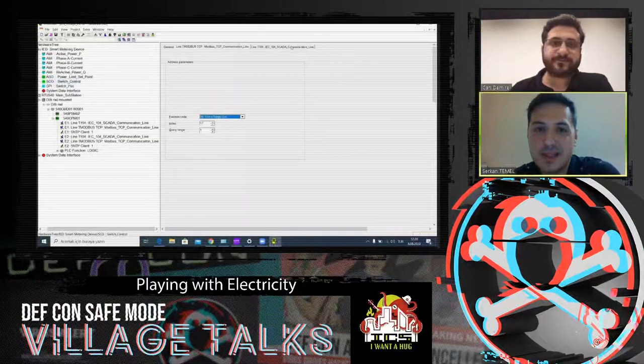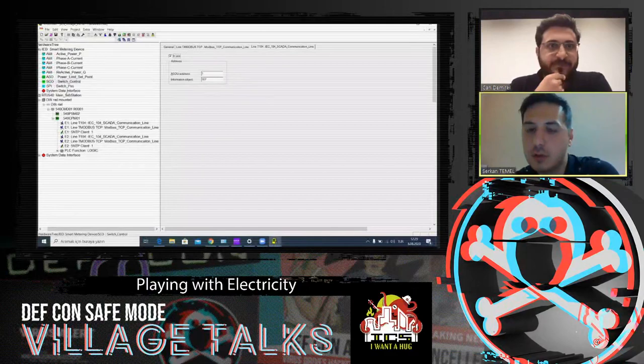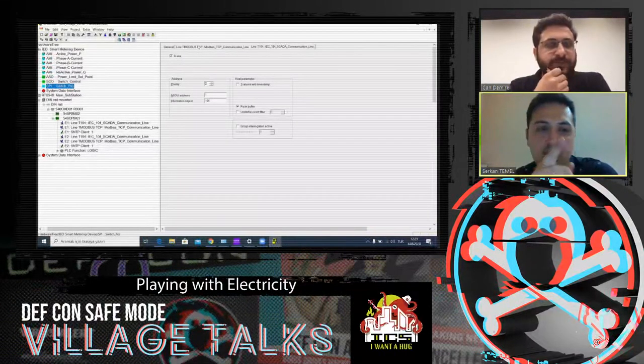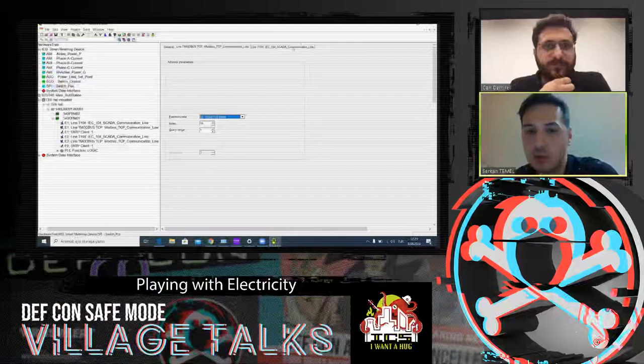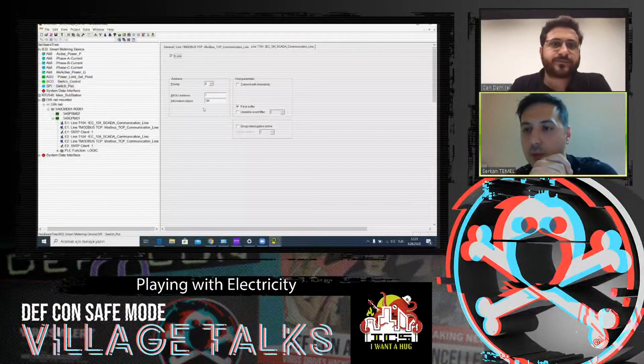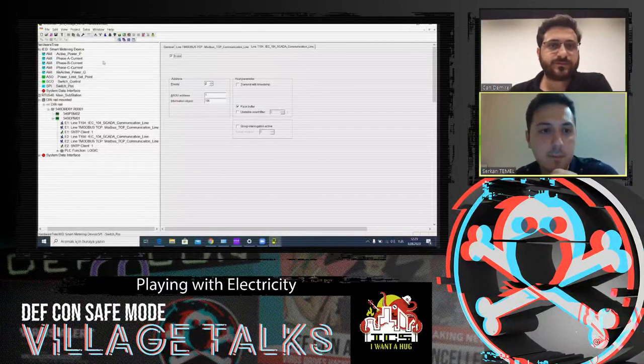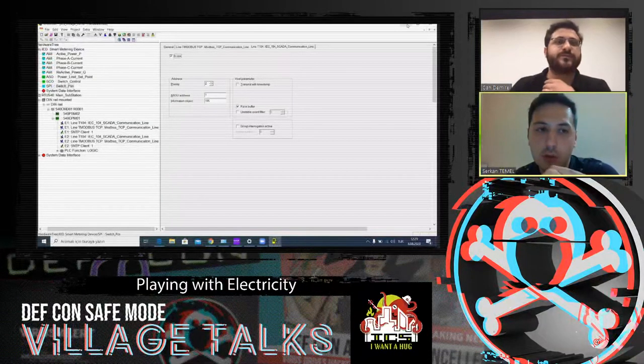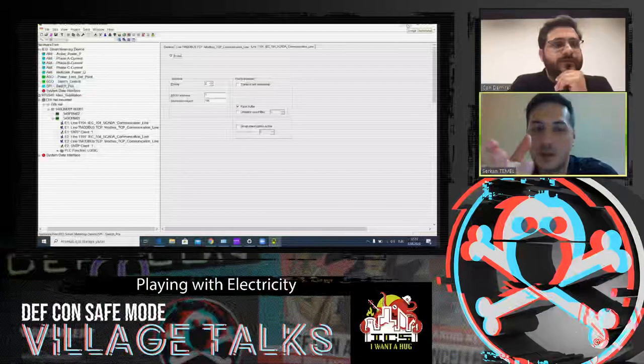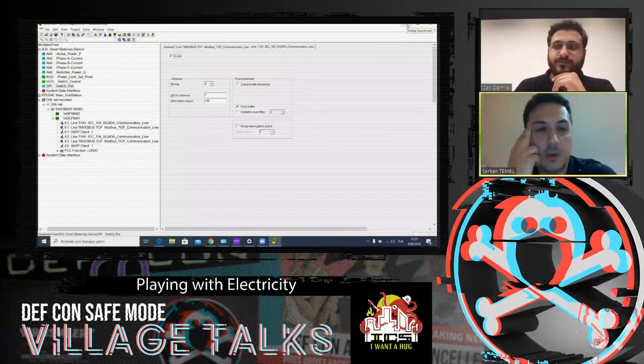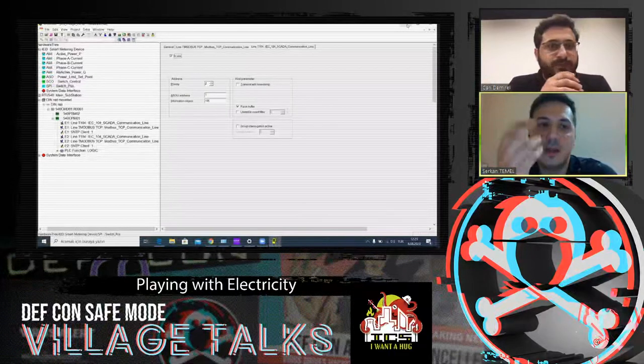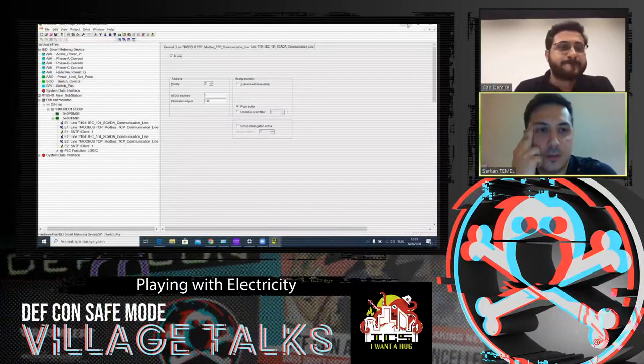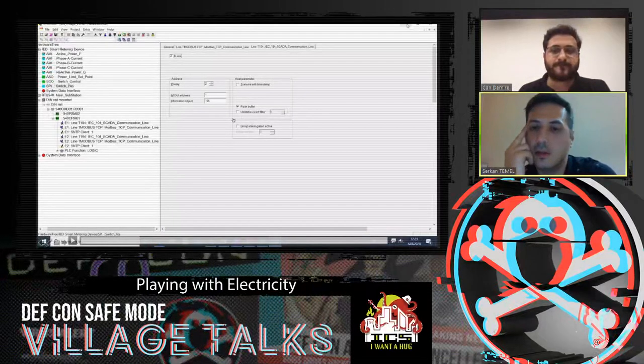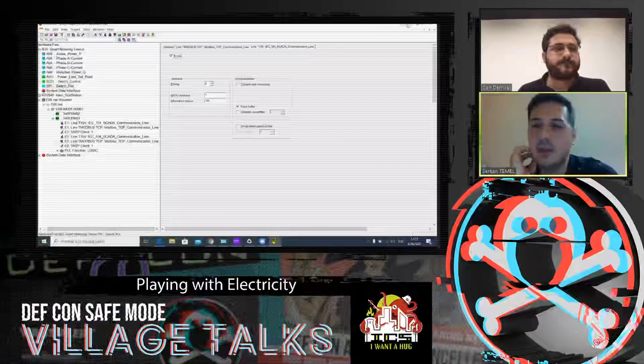This is a type of Modbus signal, as you see: force commands, signal commands, and read coil status. Read coil status is used for single point information, digital input like the position of a circuit breaker. Switch control means sending a control command to the circuit breaker. Then power limit set point, and other metering information: phase A current, phase B current, phase C current. It's a very simple model of a substation.